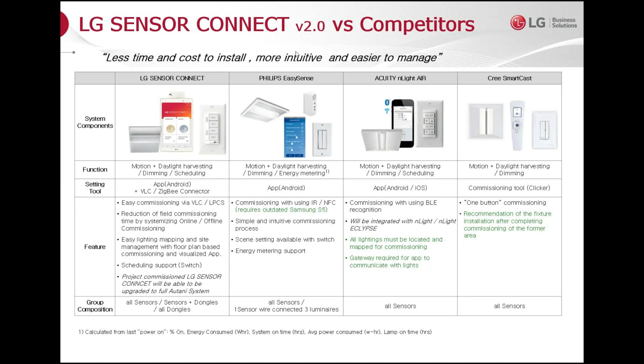We really like the idea of one-button commissioning, so we try to mimic that in our floor commissioning. If you're on a certain floor and press the commissioning button, it will go through and try to commission all the lights in all the locations within 130 feet. If you're too far away from a certain area, you simply walk over to that area and the lights will get commissioned. With Cree, you have to have all the lights installed first before you begin commissioning. With Sensor Connect, you can go as you install, or come back at the end and program everything once they're all installed. Similarly, they require all sensors, whereas we can combine sensors and dongles.